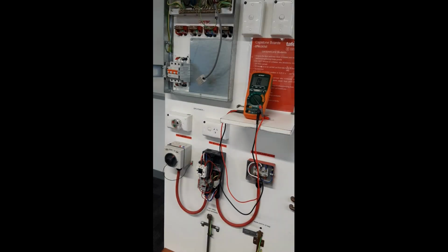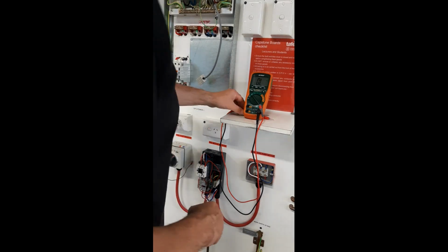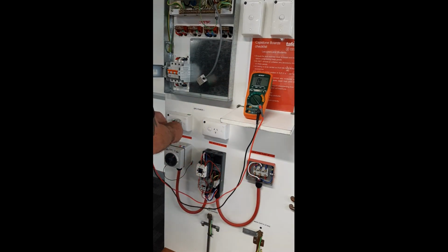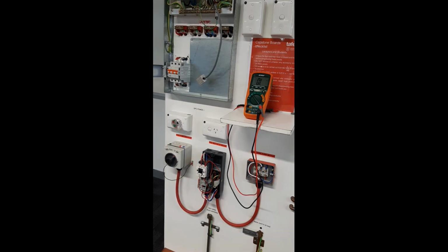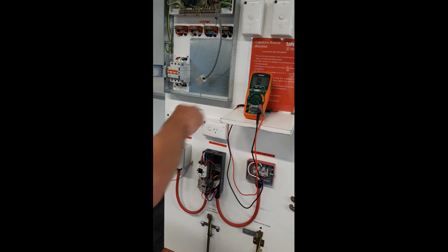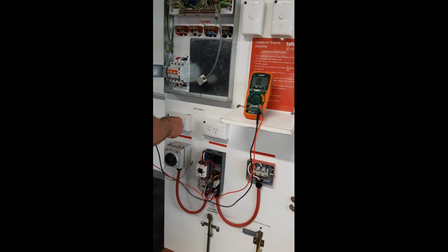Test between the active and the earth. The result should be 10 ohms. The switch turns the continuity on and off. Test between the neutral and the earth. The result should be 5 ohms. The switch should not activate at all. The switch is in the active conductor.